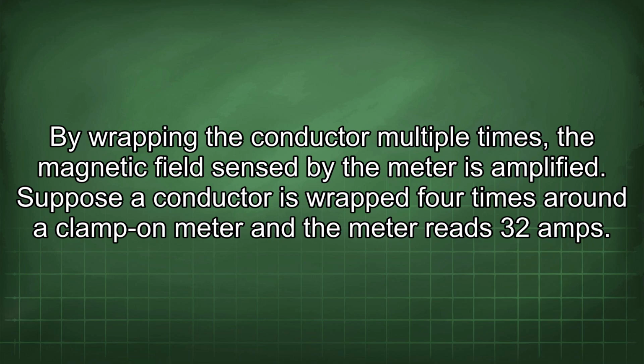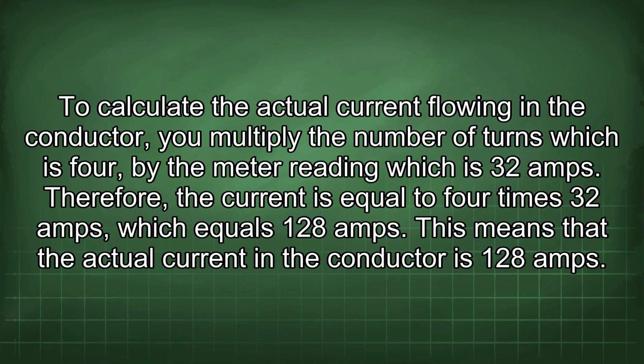Suppose a conductor is wrapped 4 times around a clamp-on meter and the meter reads 32 amps. To calculate the actual current flowing in a conductor, you multiply the number of turns, which is 4, by the meter reading, which is 32 amps. Therefore, the current is equal to 4 times 32 amps, which equals 128 amps. This means that the actual current in the conductor is 128 amps.